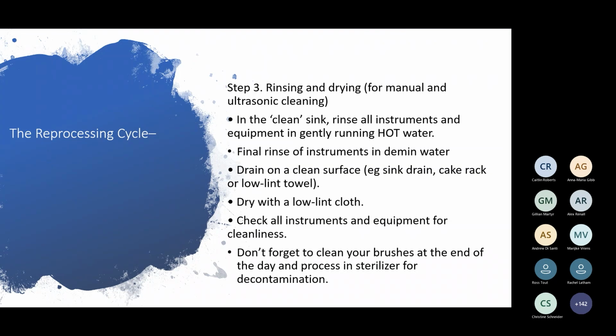Once we've done that final rinse of our instruments, we drain them on a clean surface, either a sink drain, cake rack, or a low lint towel. Now, please don't continue to use the same low lint towel all day so that it's sopping wet and it's not going to do anything. You should be drying your instruments immediately. You shouldn't be leaving them sit there wet on a wet cloth in the sterilizing room until you can get back to them. The reason that I'm saying this to you is because if you're leaving your instruments in a wet environment, then you're potentially allowing bioburden to develop on your instruments.